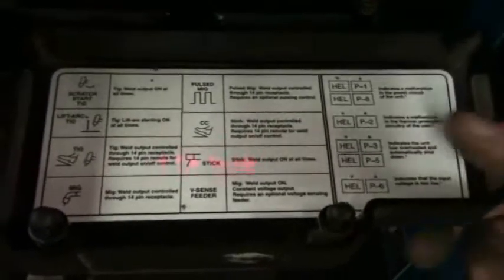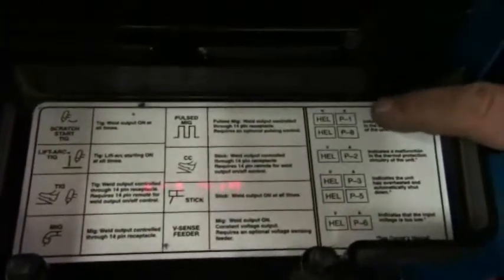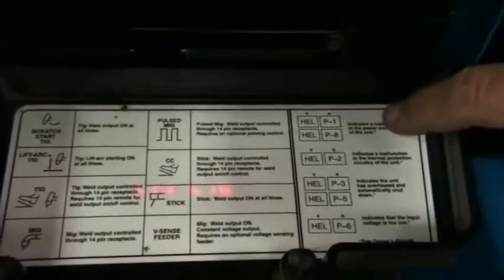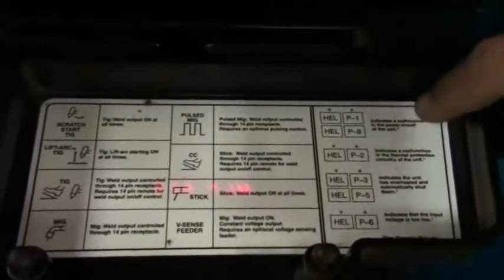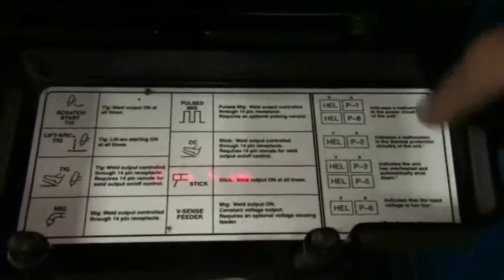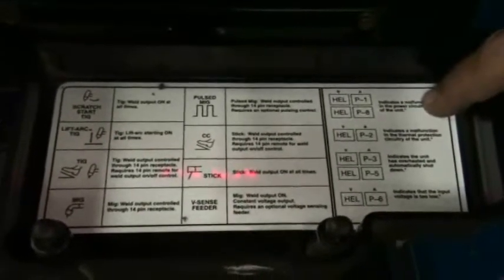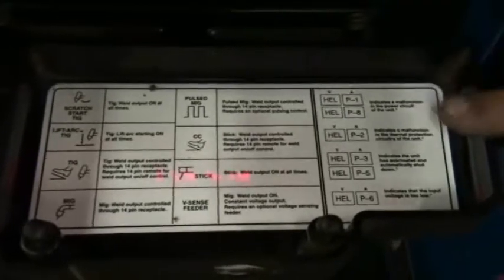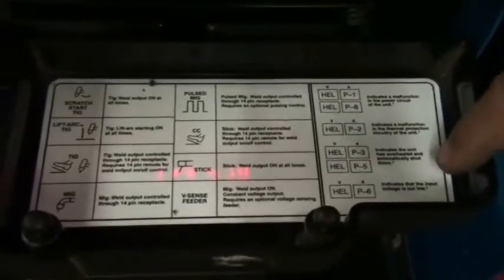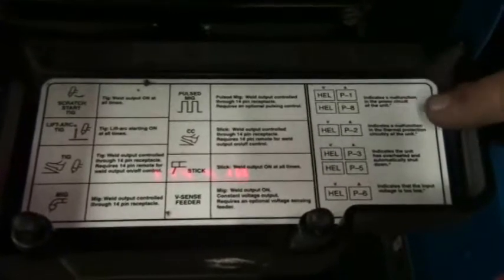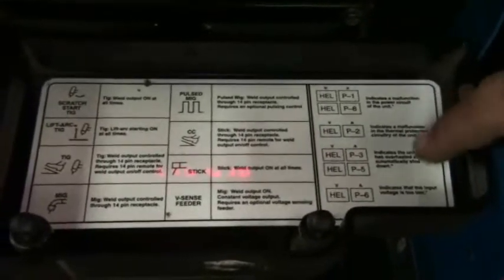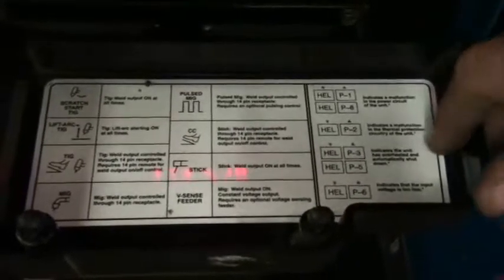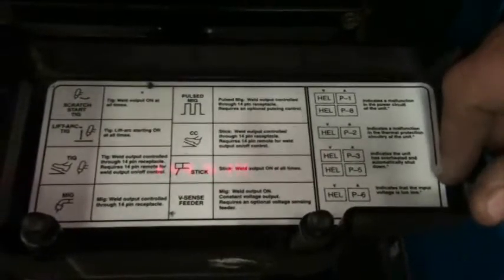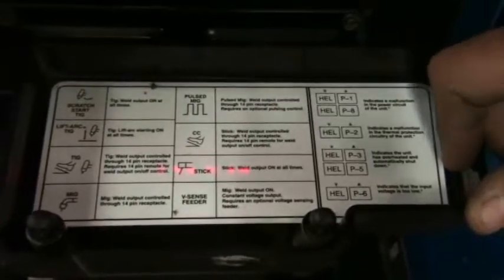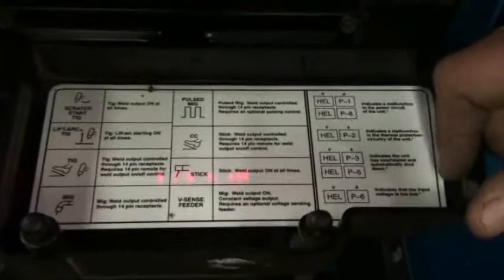This is the front panel door. It covers the switches and everything so they don't get destroyed. But also when you go to power this thing up, if you come up with a fault, which is a help, it tells you exactly what the problem is. If you have a fault where the power's down, it'll come up with the fault, and it'd be P6, which indicates the input voltage is too low. That way you have an idea. Maybe you could check the connection to make sure you don't have a loose leg somewhere, possibly, because all these are checked before they go out. They're all load tested and everything before they go out.